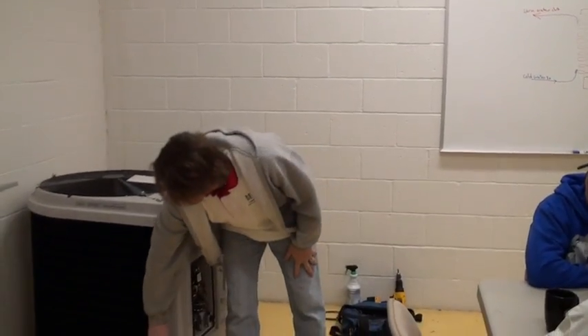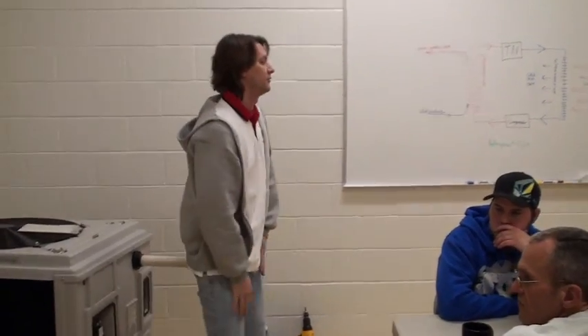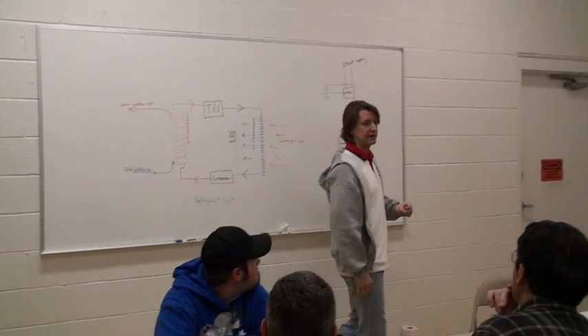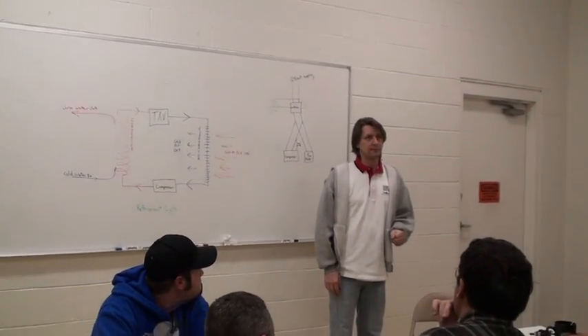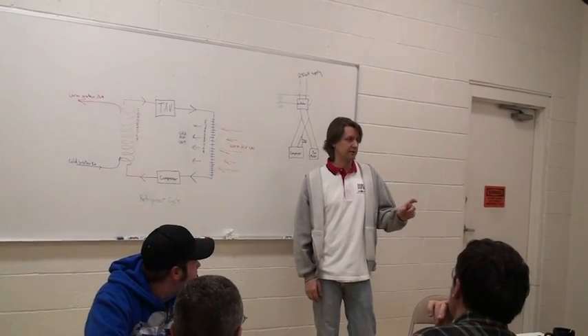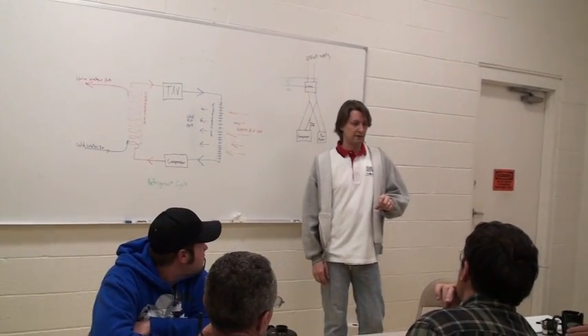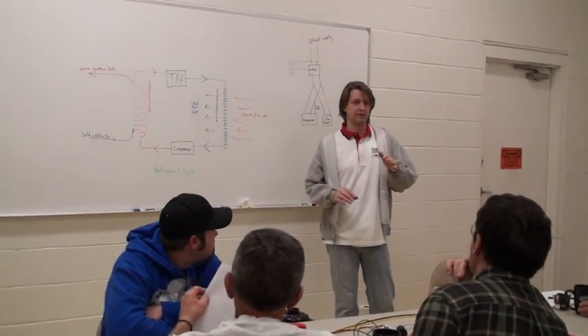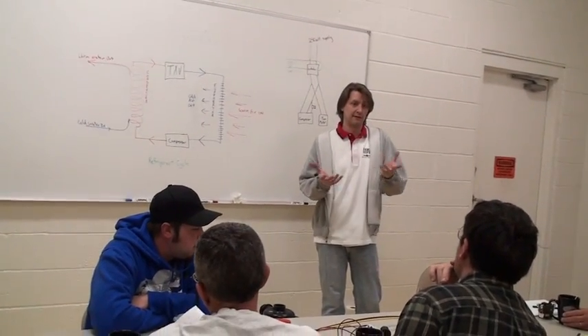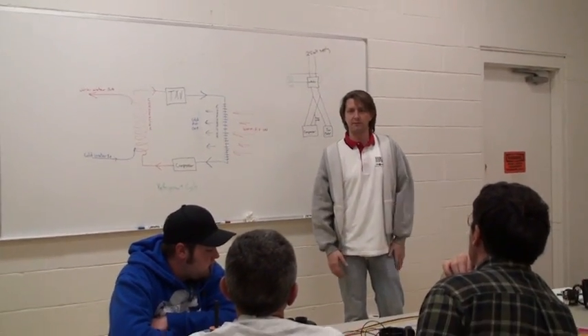And they're not interchangeable, the two refrigerants. They're not, you can't swap one out for the other. There is a drop-in replacement for R22. It's called R422B. It's marketed, I think, as New 22B. There was a New 22, and then there's now a New 22B. The R number never changes. That New 22 is like Puron, it's just a trademark. It's like Kleenex, it's really tissue, but everyone knows what you're talking about when you say Kleenex.